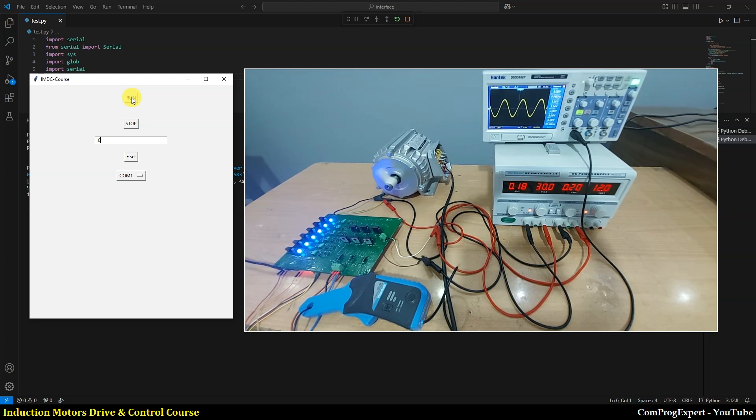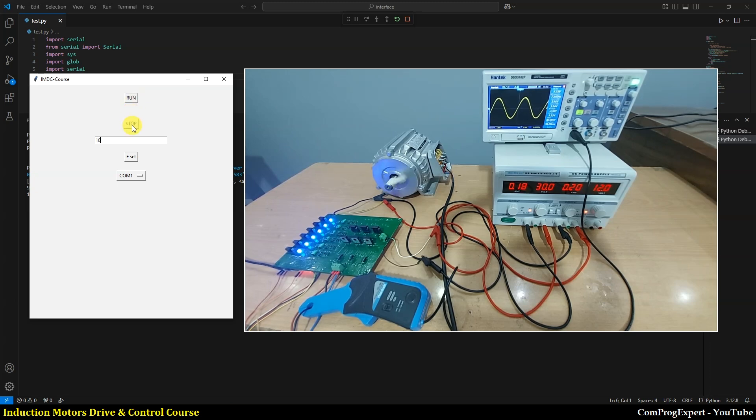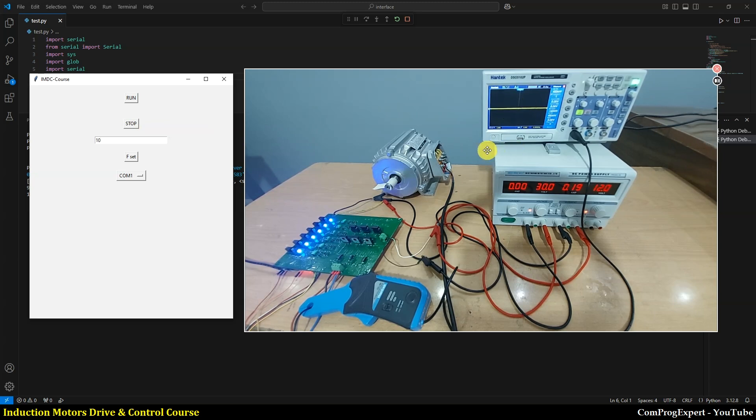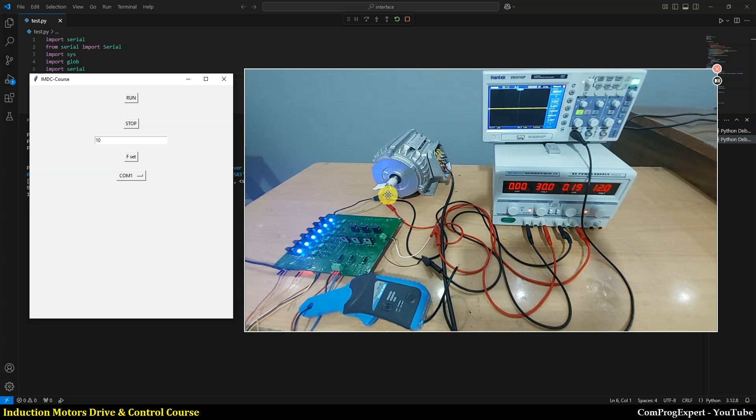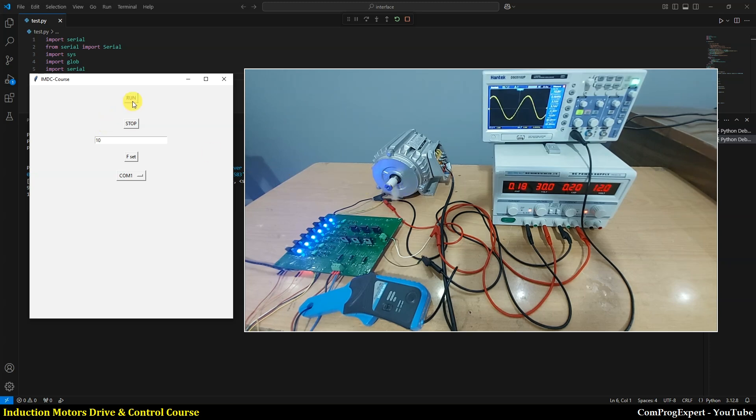So now let's turn off the motor. Here as you can see, we have gradual reduction in the value of the frequency, and finally we stop the timer when the frequency is lower than the minimum value. So again, I run the motor and I am going to change the motor speed during the working of the timer.